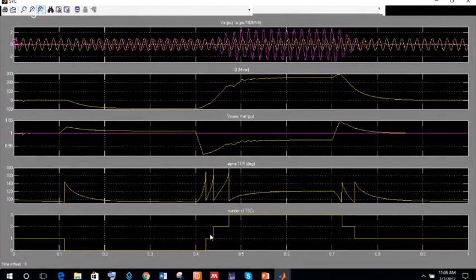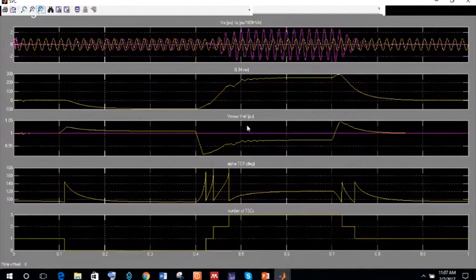That is done by introducing capacitor banks, switched in one by one. That is shown by this, and with this there is an increase in reactive power, and this continues till the voltage is less, and when again the voltage is greater than the reference, the same should follow: the thyristors should disconnect, or switch off the capacitor banks, and the increased power should be absorbed, so the reactor should be brought back in the circuit. So this is the way SVC works. Depending on the loads, depending on the requirement, the value of inductance and capacitor bank should be decided.